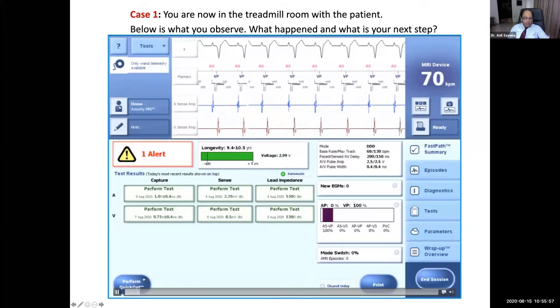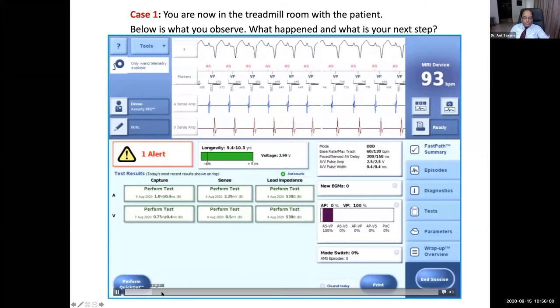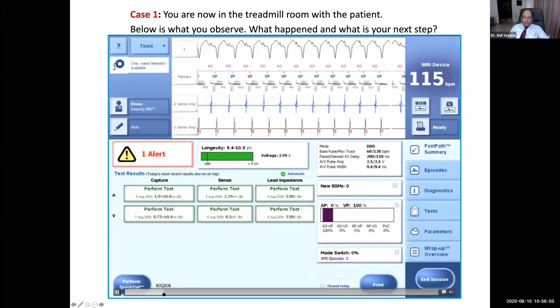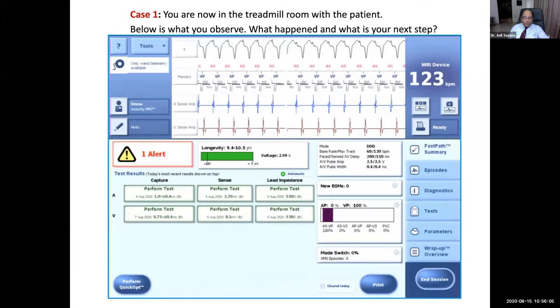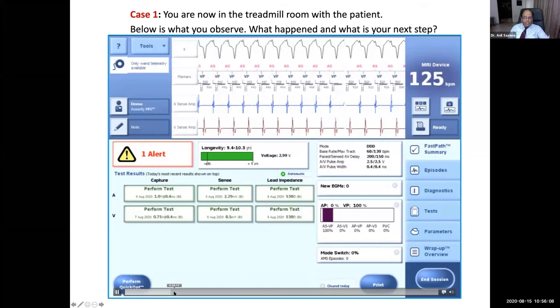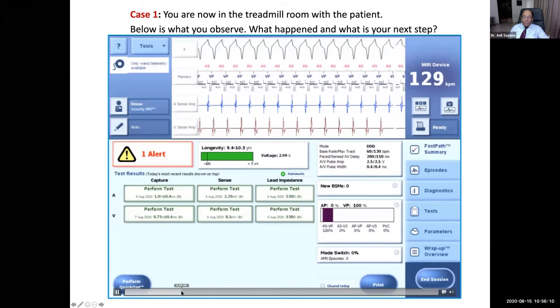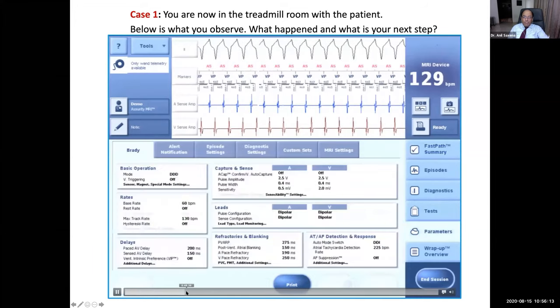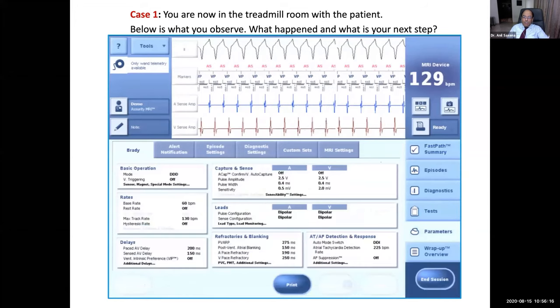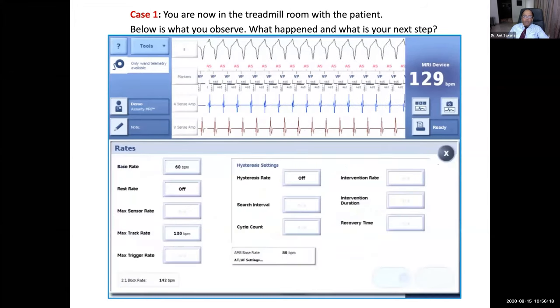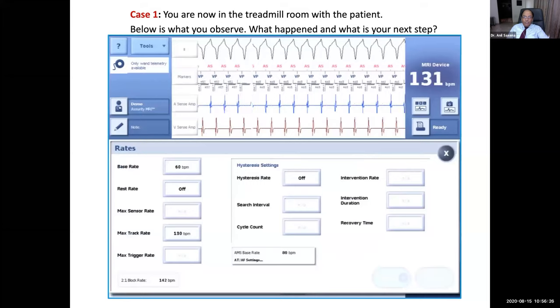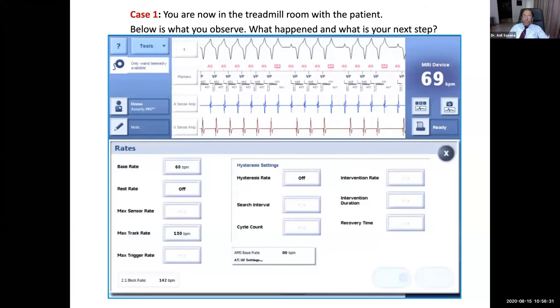As the patient exercises and the heart rate increases up to 120, we can see there is one-to-one conduction. But as the heart rate goes beyond 130, the patient is expected not to continue increasing the heart rate, but the pacemaker develops a pattern similar to Wenckebach. We call it pseudo-Wenckebach because it is happening due to the pacemaker, and the heart rate remains fixed at 130—the pacemaker tries not to increase the heart rate beyond the set upper tracking rate.